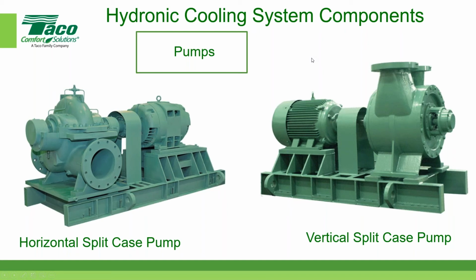Yep. Why does the base mounted pump have a size difference from suction to discharge? Because in order to make the pump more efficient, when the guys from our engineering group design the impellers and the volute, they are actually increasing the velocity as it exits the pump by going from a larger diameter to a smaller diameter. And that velocity is ultimately converted into static pressure, which gives us the ability to move the fluid through the piping system. So it has to do with the relationship of the rotating impeller and the velocity of the fluid as it makes the conversion from velocity pressure into static pressure.